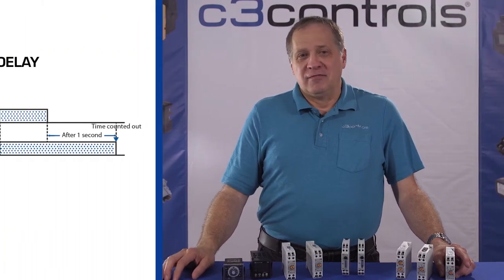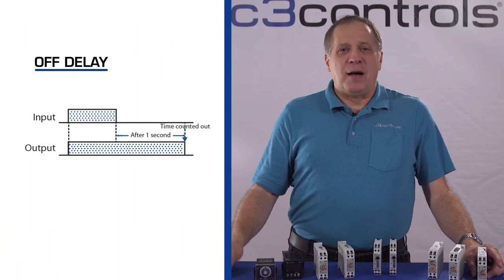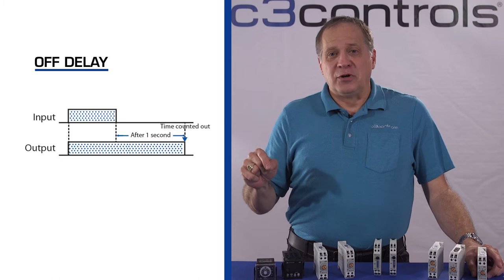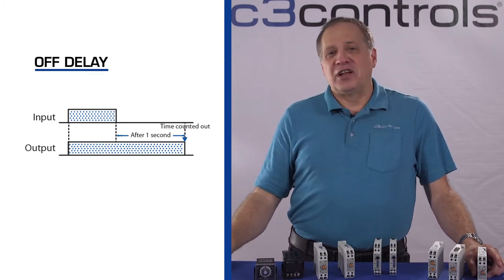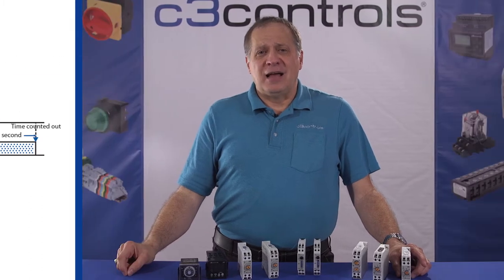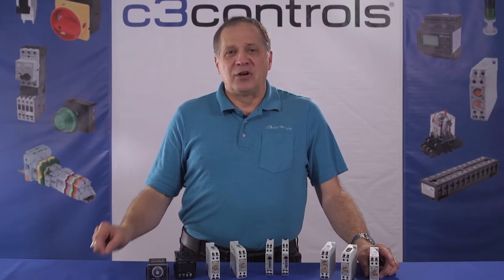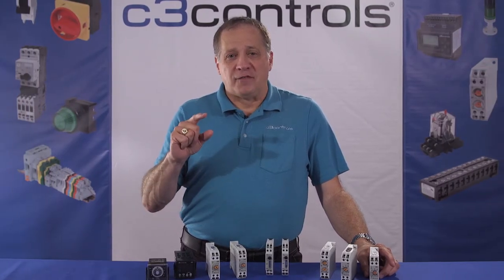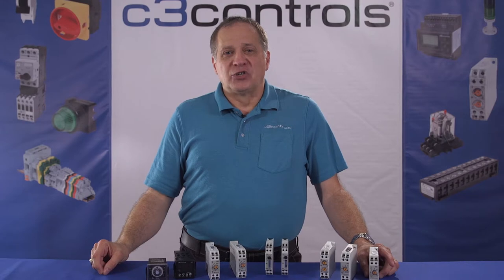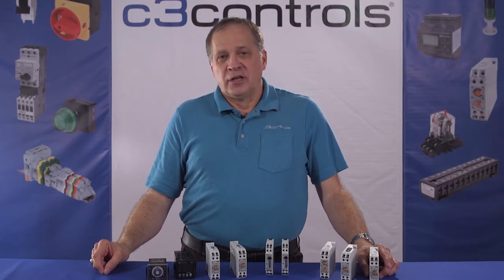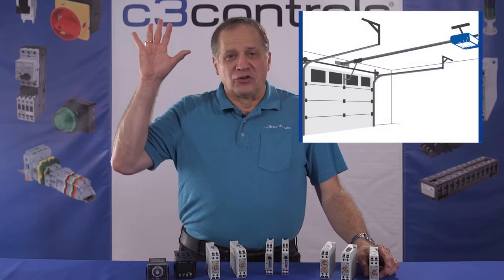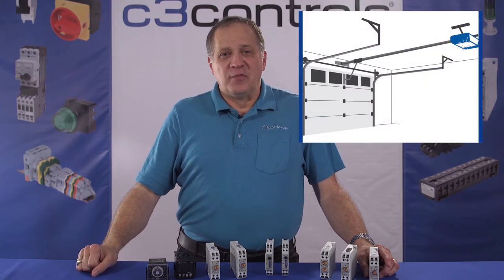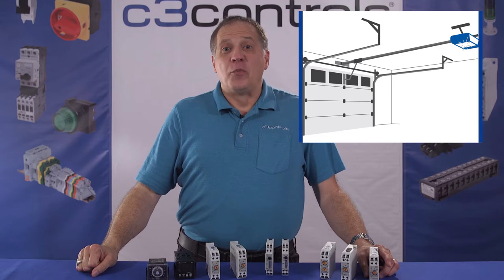Off delay. With off delay operation, the output turns on at the same time as the input, and then the output turns off when the timer contacts open after the set time has expired. The set time is calculated from when the timer input turns off. This name is used because there is a delay between when the input turns off and when the output turns off. For example, when you open or close your garage door, the ceiling light turns on and remains lit for a few minutes after you open or close the door.